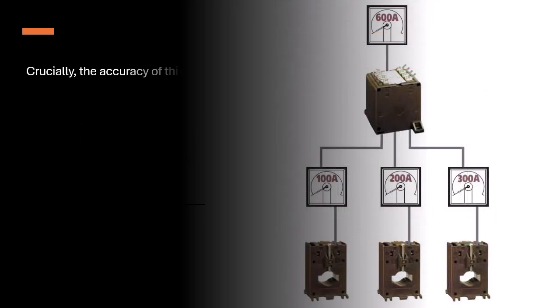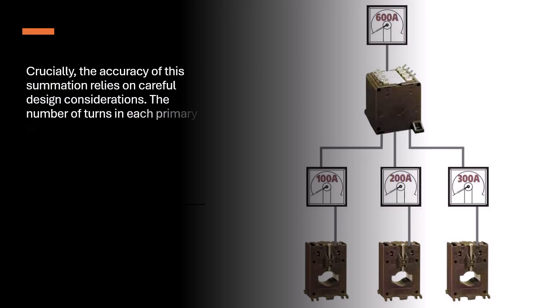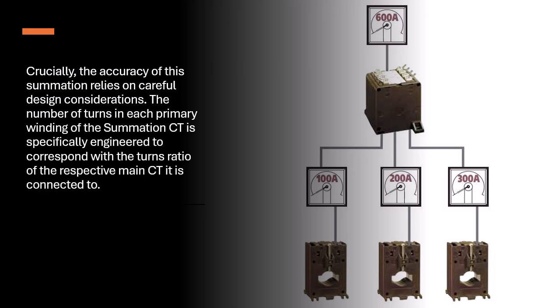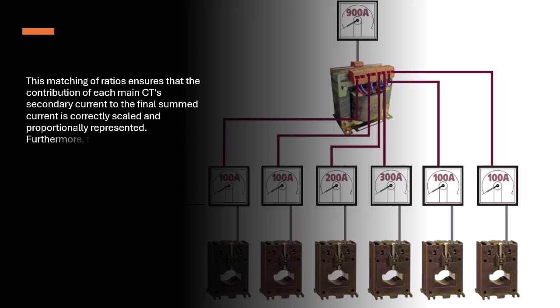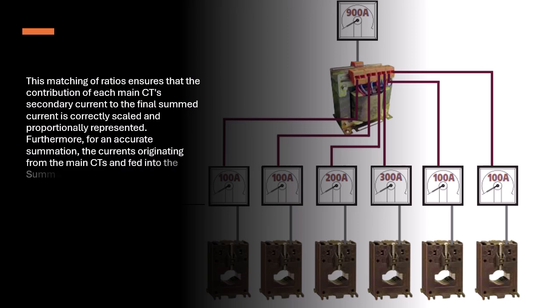The accuracy of this summation relies on careful design considerations. The number of turns in each primary winding of the summation CT is specifically engineered to correspond with the turns ratio of the respective main CT it is connected to. This matching of ratios ensures that the contribution of each main CT's secondary current to the final summed current is correctly scaled and proportionally represented. Furthermore, for an accurate summation, the currents originating from the main CTs and fed into the summation CT's primary windings must be in phase.